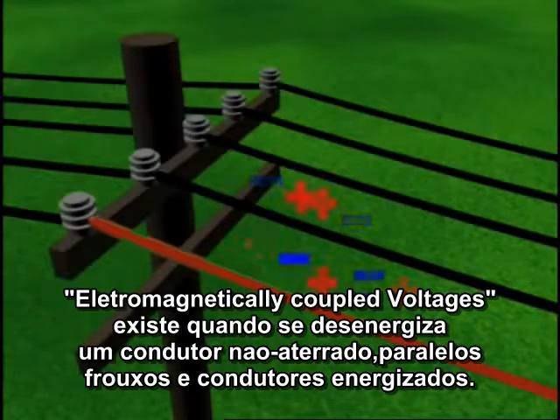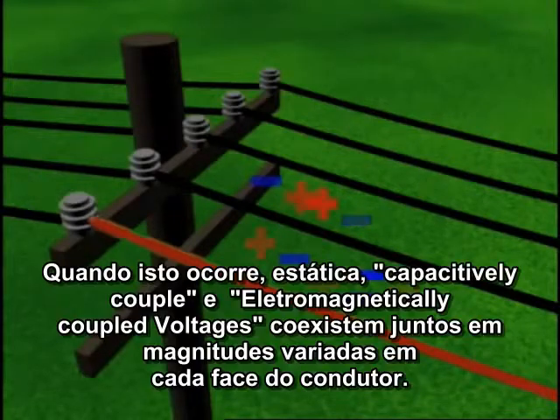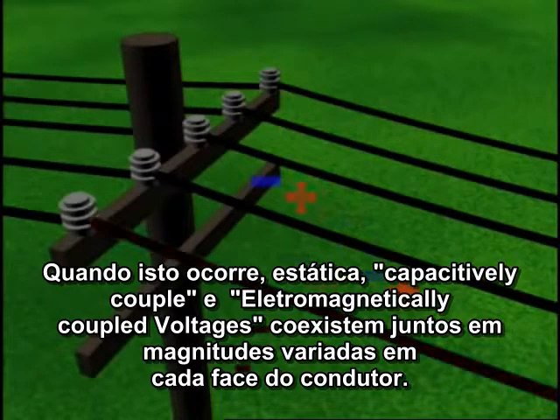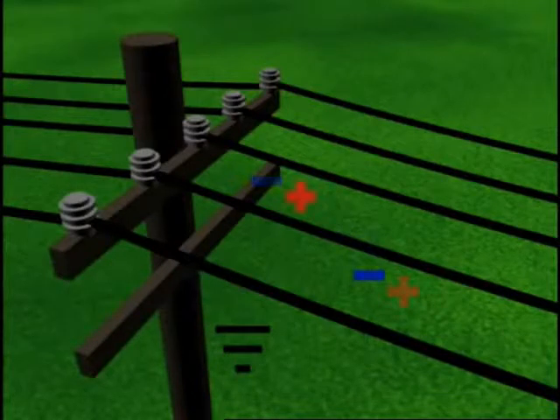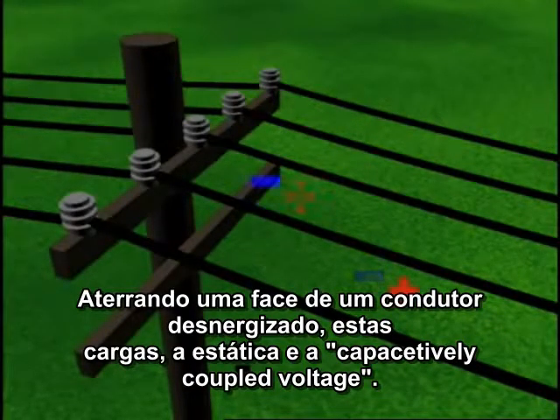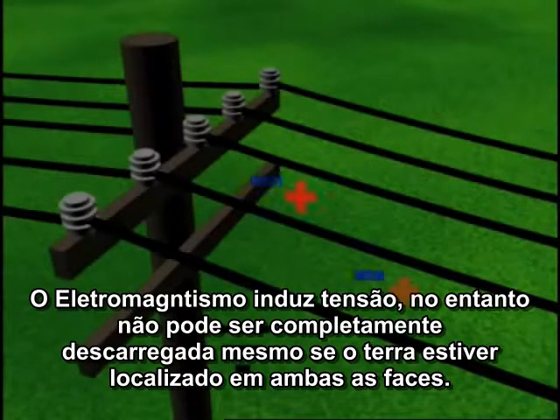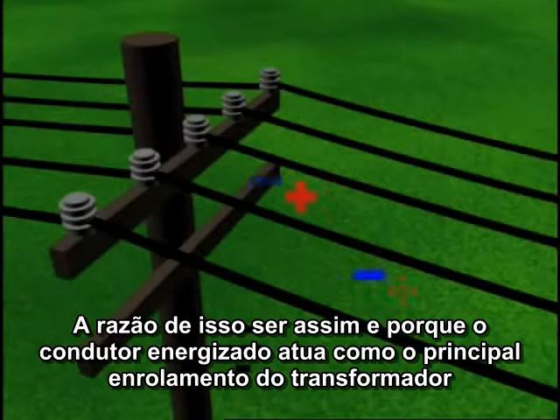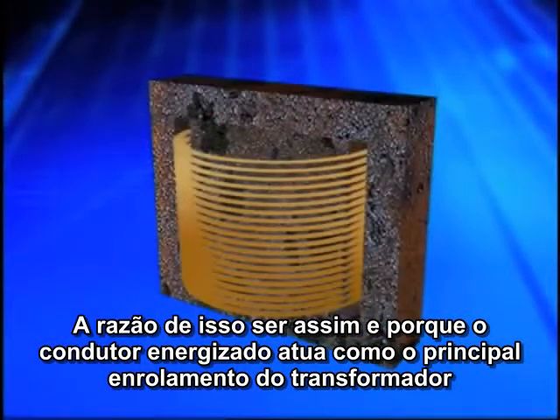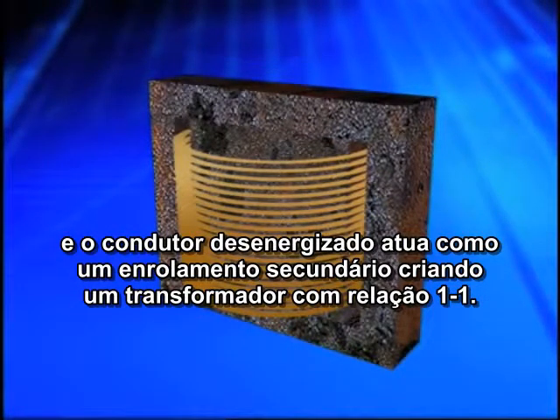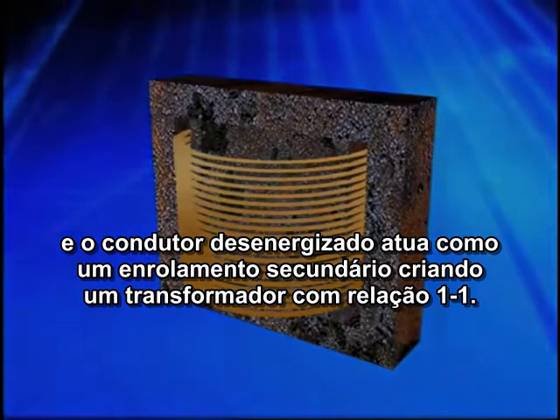Electromagnetically coupled voltages exist when a de-energized, non-grounded conductor closely parallels an energized conductor. When this occurs, static, capacitively coupled, and electromagnetically coupled voltages all exist together in varying magnitudes on each phase conductor. Grounding one end of the de-energized conductor discharges the static and capacitively coupled voltages. The electromagnetically induced voltage, however, cannot be completely discharged even if grounds are placed on both ends. The reason is that the energized conductor acts as the primary winding of a transformer, and the de-energized conductor acts as the secondary winding, creating a transformer with a 1-to-1 ratio. A low value of mutual inductance is created.